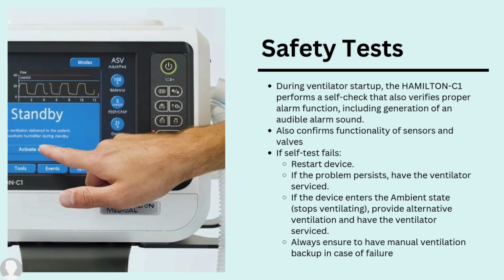If the self test fails, we must restart the device. If the problem persists, have the ventilator serviced. If the device enters the ambient state in which it stops ventilating, provide alternative ventilation and have the ventilator serviced. Always ensure to have manual ventilation backup in case of failure.